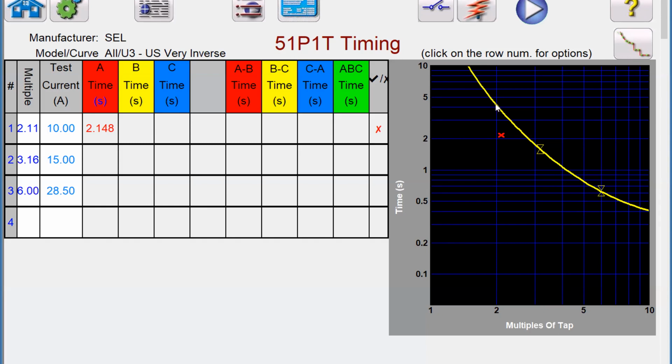So if I hit run and select here, as Mohit came on and addressed, I have a communication issue going from my PC to my relay. I'm not able to perform the element masking. So I would mask the 51P1T to OUT107 of the relay using the AcSELerator software.